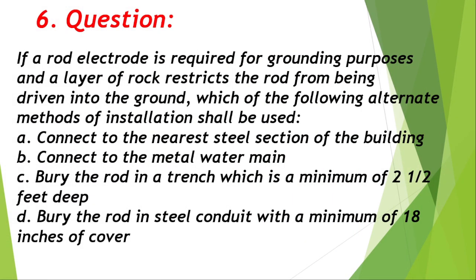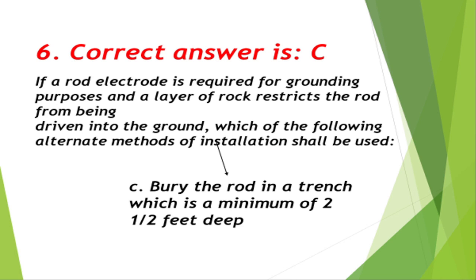Question number 6: If a rod electrode is required for grounding purposes and a layer of rock restricts the rod from being driven into the ground, which of the following alternate methods of installation shall be used? A. Connect to the nearest steel section of the building, B. Connect to the metal water main, C. Bury the rod in a trench which is a minimum of two and a half feet deep, D. Bury the rod in steel conduit with a minimum of 18 inches of cover. Correct answer is C, bury the rod in a trench which is a minimum of two and a half feet deep.